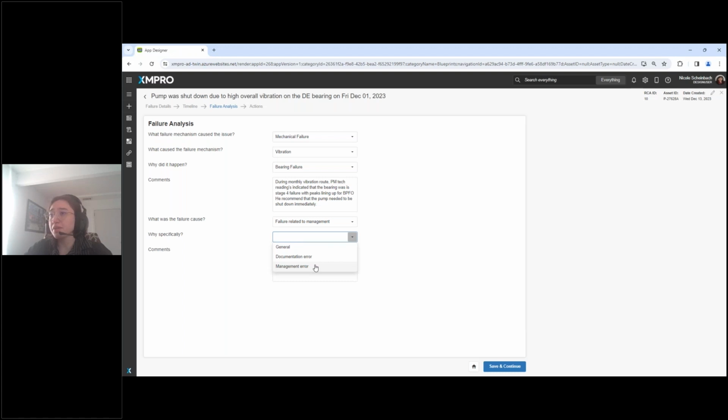So the management of the PMs needs to be reevaluated. You need to look at how we can ensure that critical PMs are completed or rescheduled. If it had potentially been done the day after, this may not have been an issue.